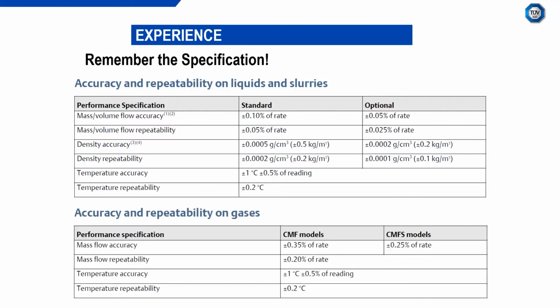So not liquid and gas together, but liquid and then separately, the exact same device could be installed in a gas line and used to measure gas. That's quite unusual. A lot of other devices, such as a turbine, wouldn't be the same. It'd be the same operating principle for the turbine meter, but it'd be a completely different device. A gas turbine meter is completely different from a liquid turbine meter, whereas with Coriolis meters, it's the same. But the mass specification for gas is 0.35%, so it's a higher specification, partly due to the lower mass of gas.